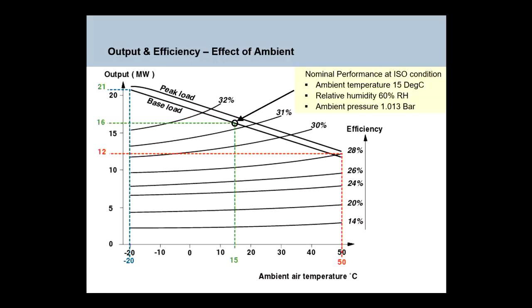Okay. One point to note, a very important point to note in operational gas turbines, is that the output of a gas turbine goes down as ambient air temperature increases. So typically in the electricity industry, we run gas turbines for short periods in very hot weather because that's when the highest demand is. That's when people run air conditioners. And the irony, or the problem for the industry, is exactly when you want gas turbines to generate power is when their output is lowest because the ambient air is hot. So you can see here on this machine, this is I think a 16 megawatt nominal machine. So at 15 degrees ambient, it will produce 16 megawatts. At 50 degrees ambient, it only produces 12, and at minus 20, it can produce 21 megawatts. Okay.